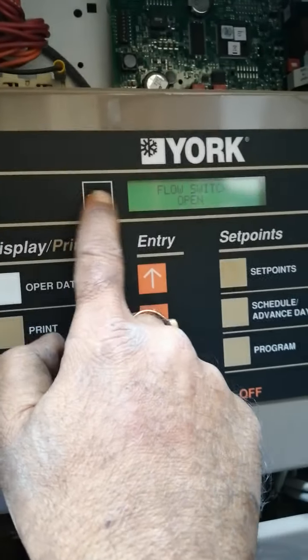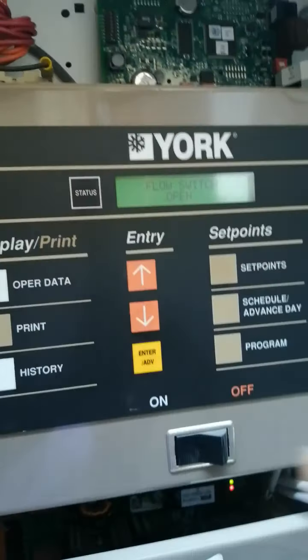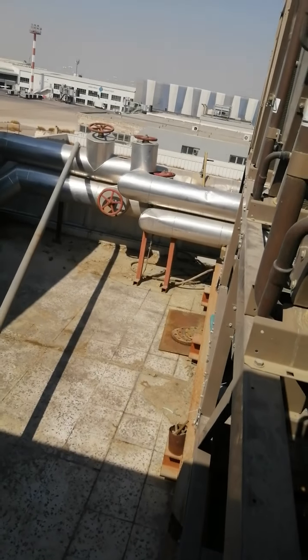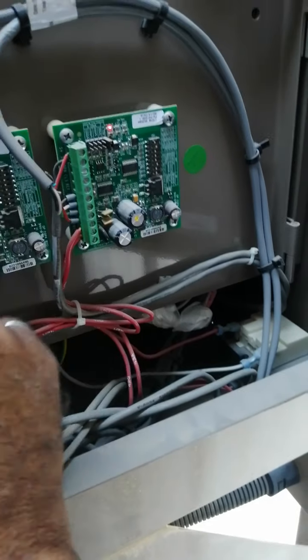That is status, what shows flow switch open. Why is that flow switch open? Because we stopped the valve of chilled water. Okay, and it is expansion valve controller. As you see, this wire is going to the electronic expansion valve from system 1 and system 2. Okay, that is our display.